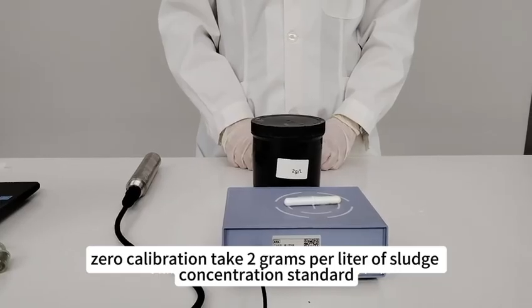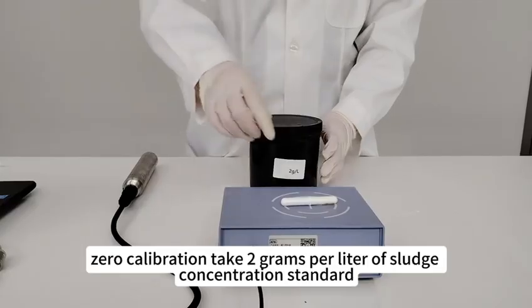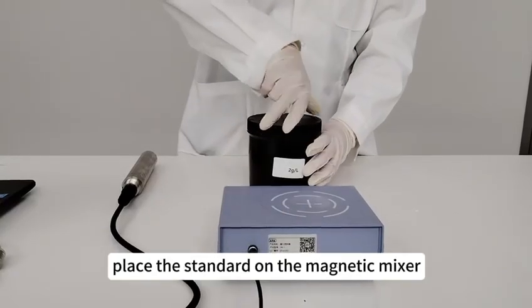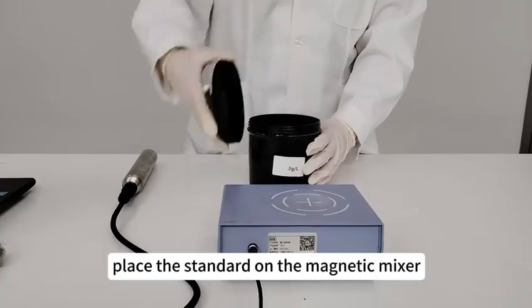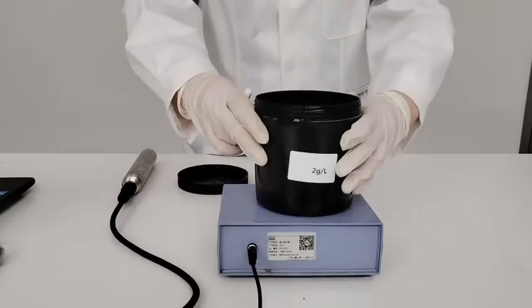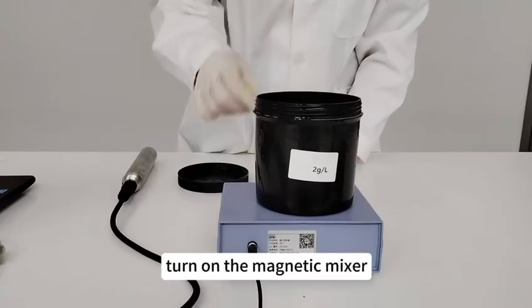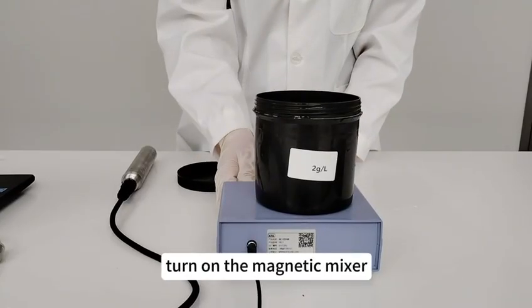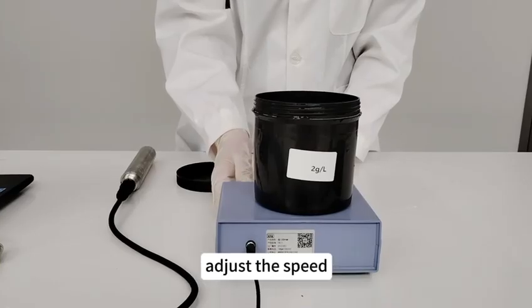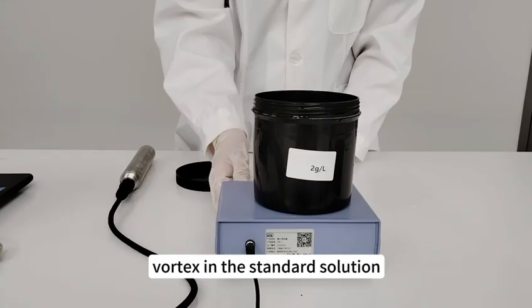Zero calibration: take 2 grams per liter of sludge concentration standard. Place the standard on the magnetic stirrer. Put in the rotor. Turn on the magnetic stirrer. Adjust the speed until there is no visible vortex in the standard solution.